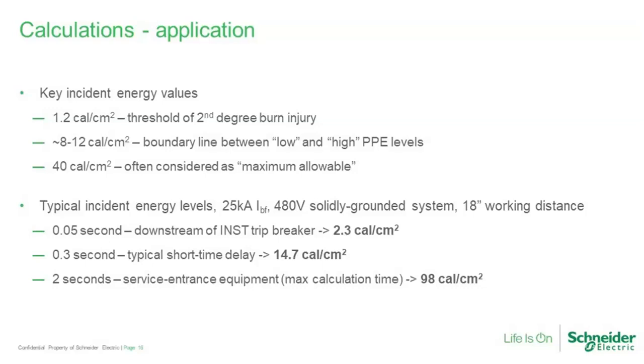It's certainly possible. Typical incident energy levels, what I've got here, some calculation parameters: 25,000 amps fault current available, so kind of middle-of-the-road, and a 480-volt system. So it's low voltage, but this is not your 120 volts at the wall outlet. 18-inch working distance, kind of an arm's length distance, which is typical for these calculations. If your breaker trips instantaneously, even with those parameters, you're above the 1.2 calories per centimeter squared, at 50 milliseconds, a typical instantaneous operating time for a circuit breaker.